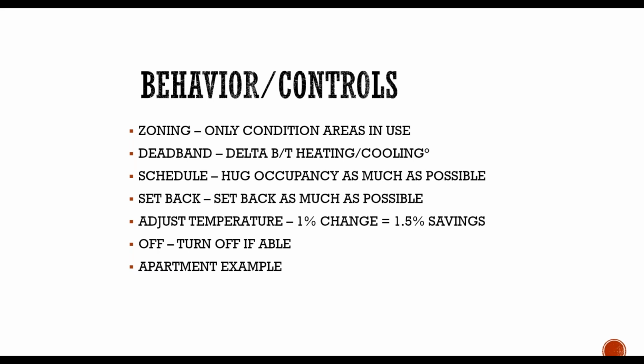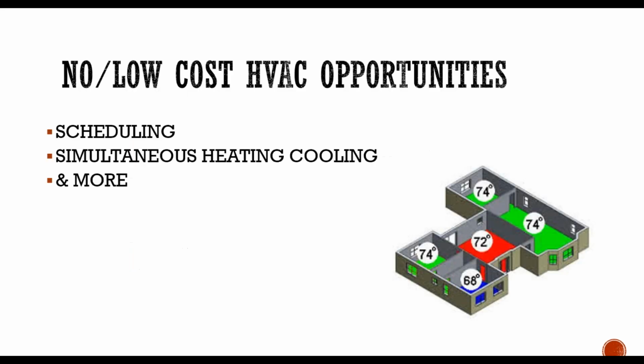Obviously, I'm a very big believer in centralized controls, like Wi-Fi enabled thermostats or direct digital controls, which are more expensive. On average, direct digital controls are $1 a square foot, whereas you're looking at $300 to $500 for a Wi-Fi enabled thermostat with software. So any way you can centralize your scheduling and your controls as much as possible, you're making your job much easier to control the largest energy-using products, right? The HVAC uses 40 to 60%.